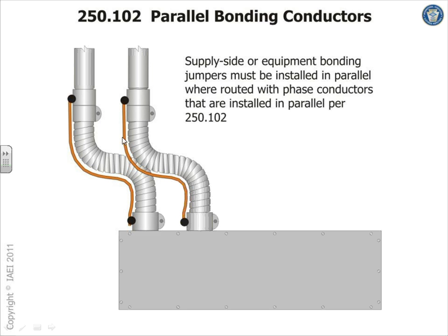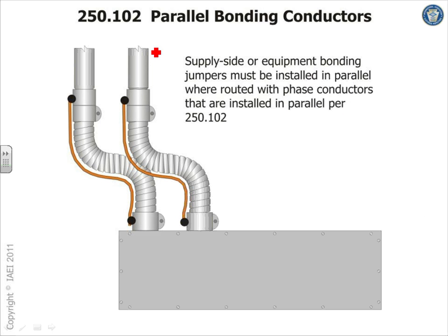In a case like this, when you size it, the conductor is phase A, phase B, phase C. Let's just say that was a 600 kcmil because we did it. Here's my 600 kcmil in each one of them, two sets parallel, and then this one in this case would be number 1/0, right? Is that what we did the example for? The supply side bonding jumper.